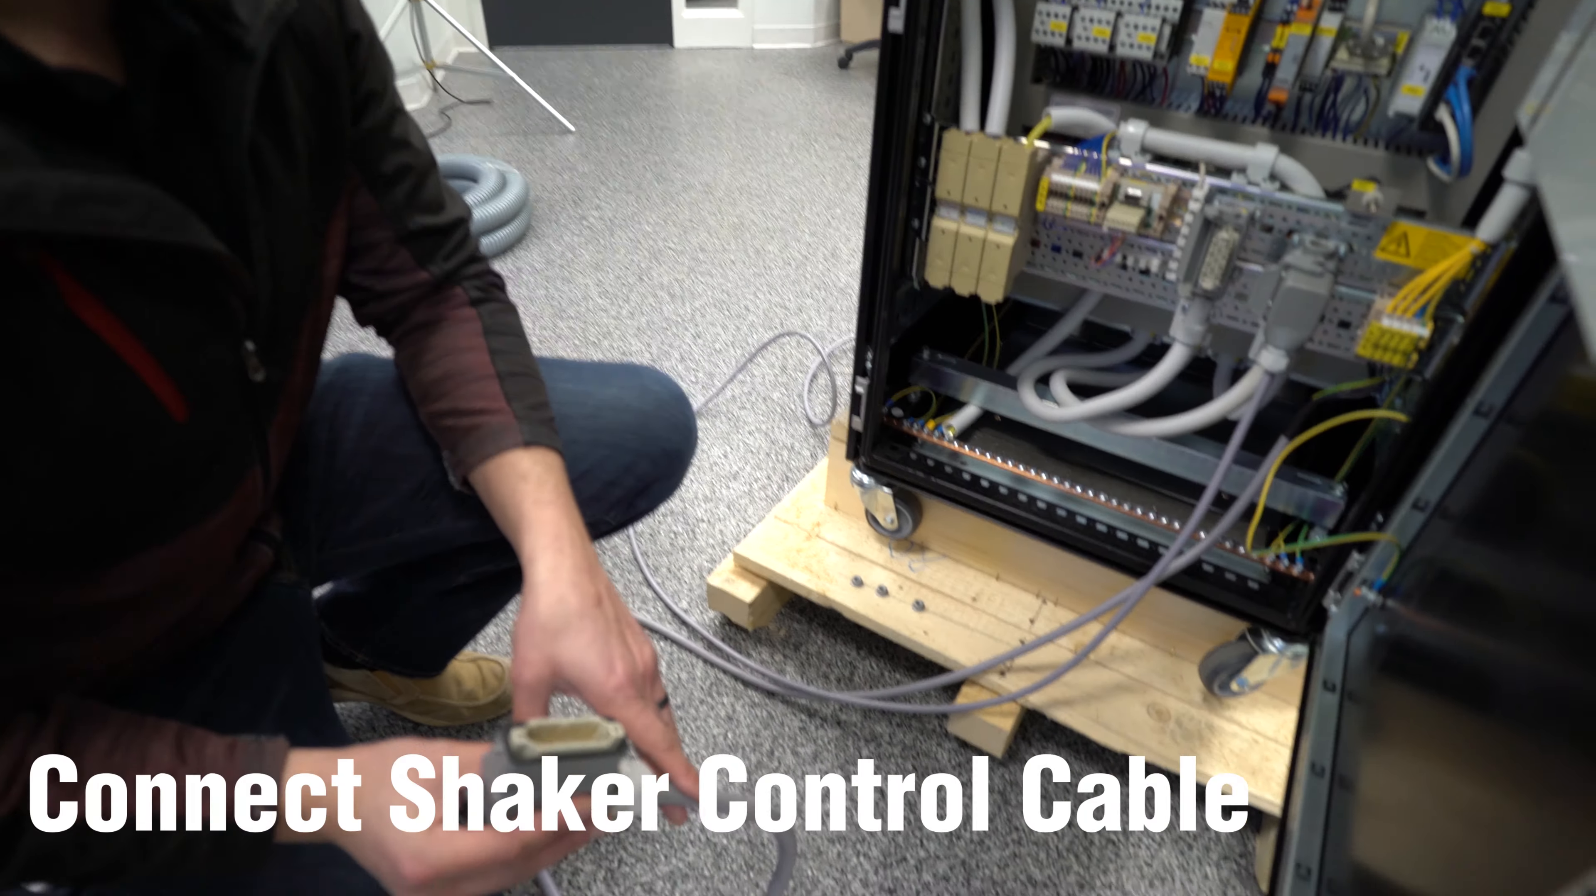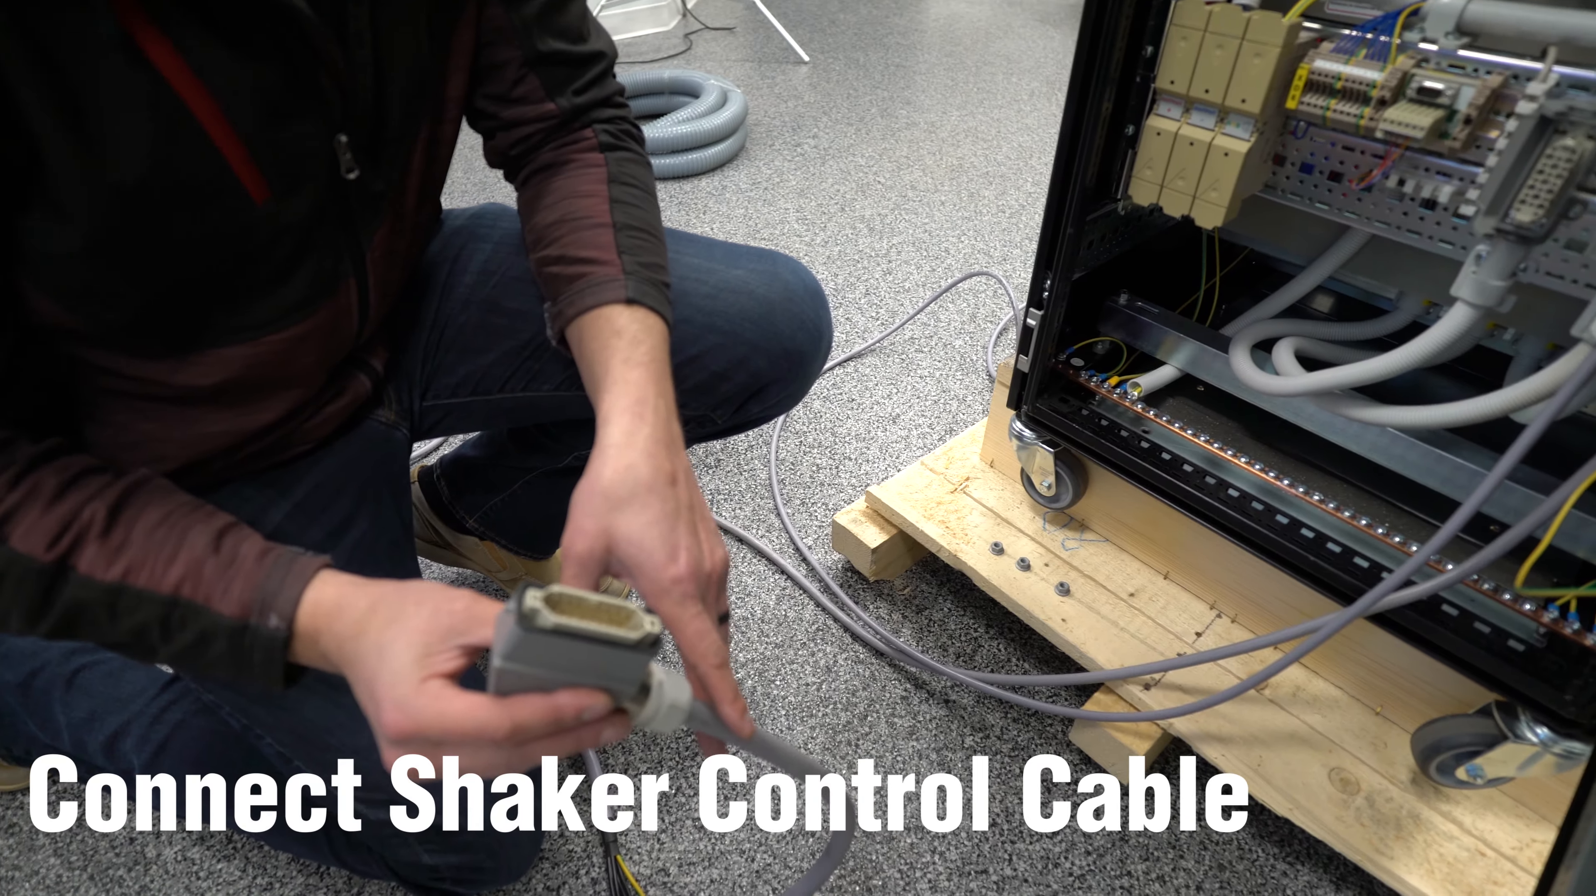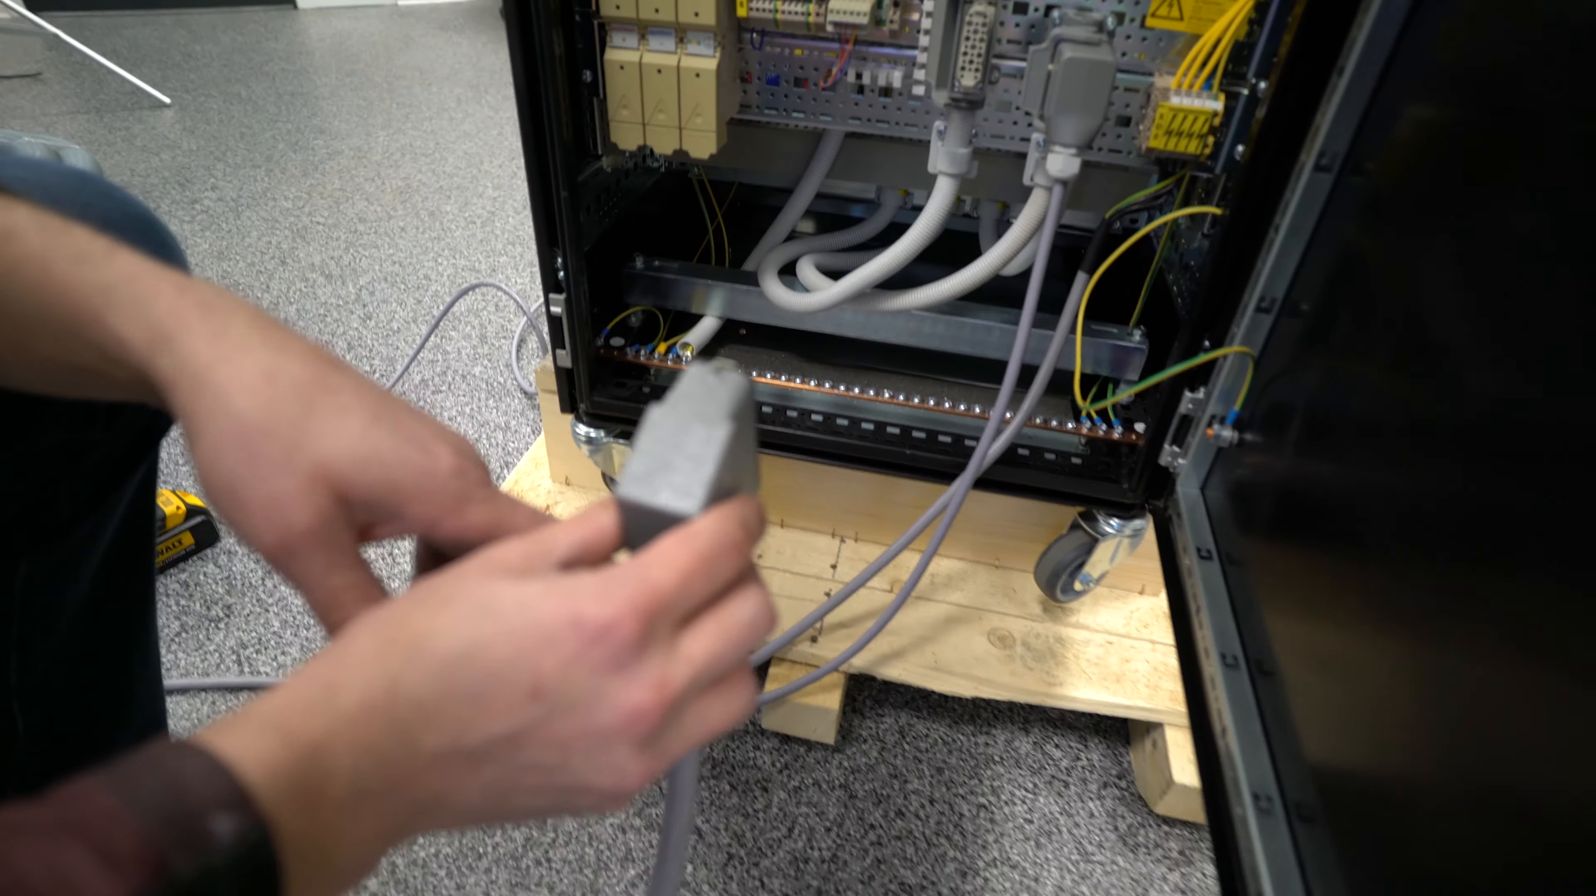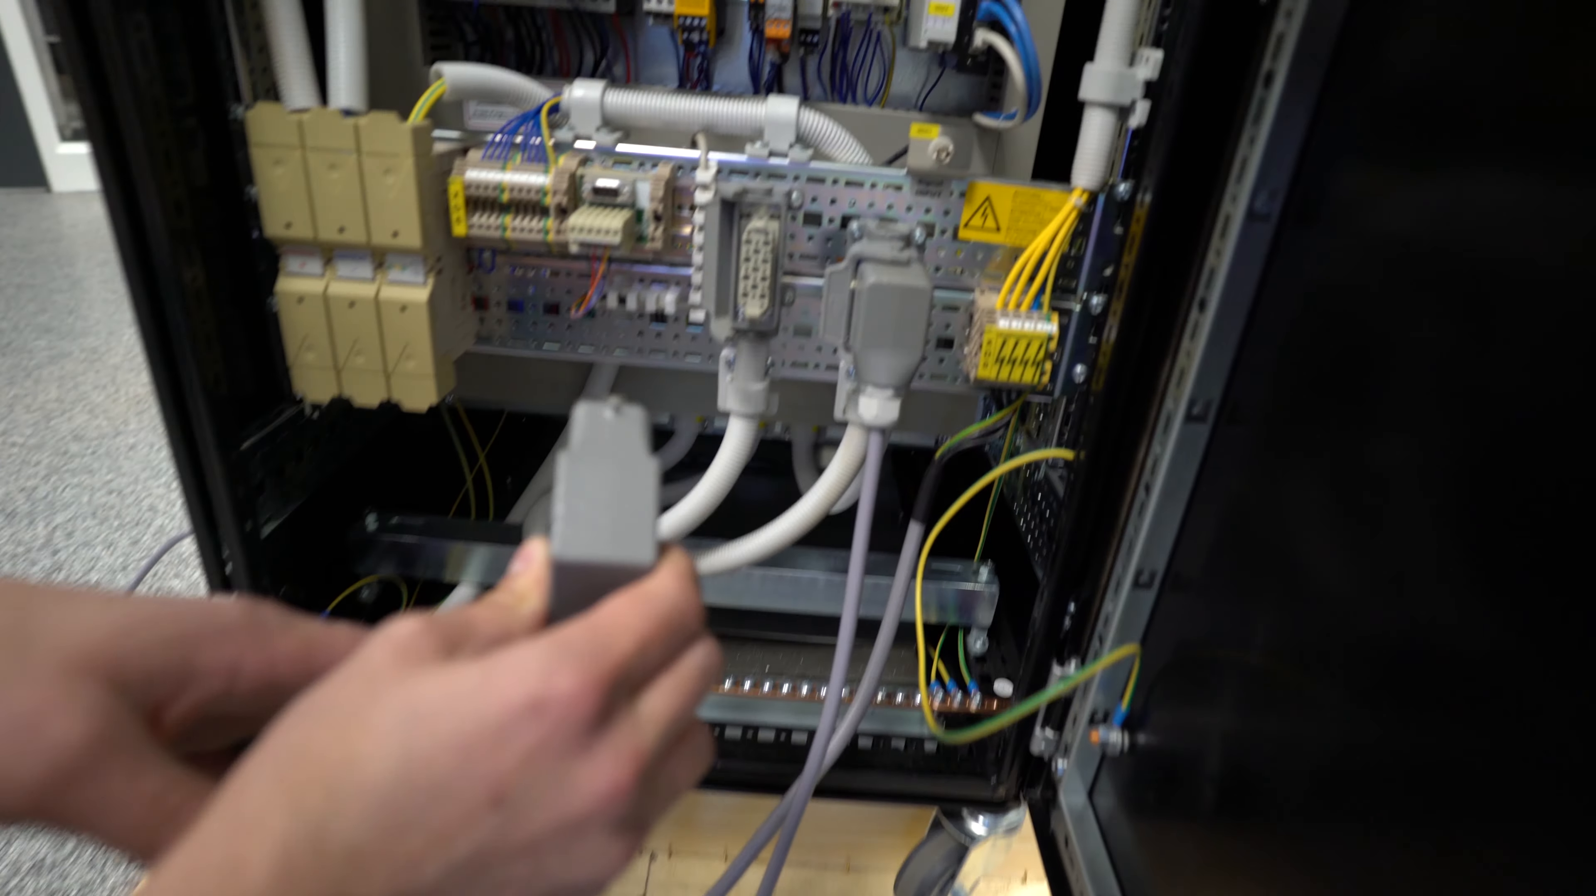The next connection we're going to make is the shaker control cable. Same thing holds true about passing through the dust cover. In our case, we're going to pass right through the door here, insert and lock.